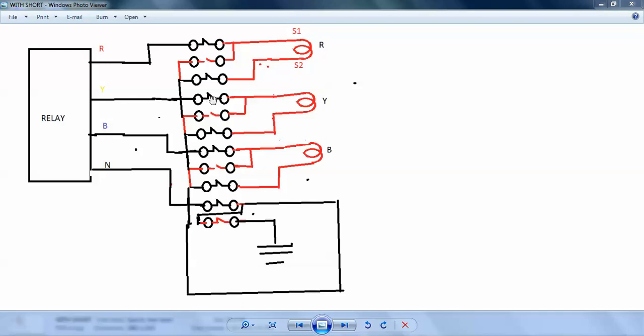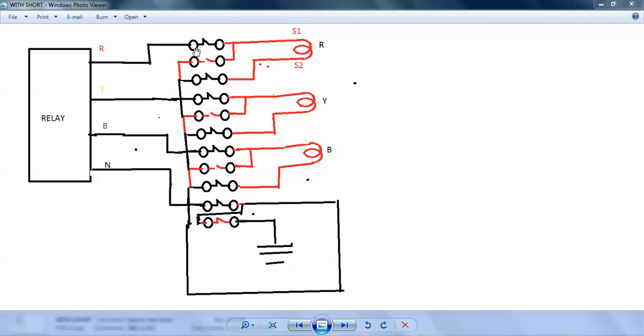Then same procedure, follow the remaining phases. You have to close the links, close the links, then open the links. Open this links, not this links, this one. I will tell you clearly: first you have to close the links, then open this one. Close the links, then open this one. Close the links, then open this one. Then open this link, neutral flow. Now you can connect your lead here. If you are going to test the relay, you can connect the lead here: R and Y, B, then neutral. So you can test relay or you can change any settings, you can do anything whatever you want.